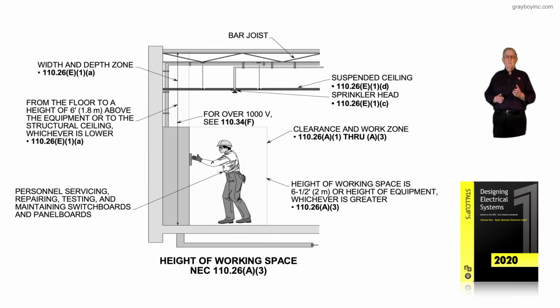And then notice it lists to the right side of the illustration at the bottom the height of the working space. It's 6.5 foot, or the height of the equipment, whichever is greater. And in this case, the equipment has a greater height than the 6.5 foot, so that's the measurement that we would go by. Now, reviewing this illustration, this is 1,000 volts or less.